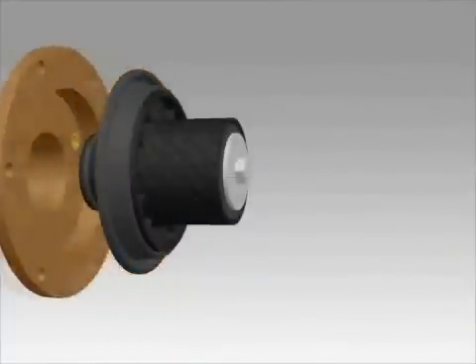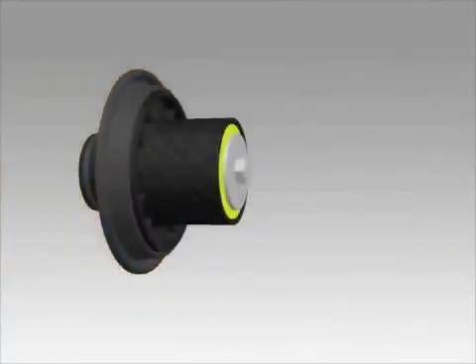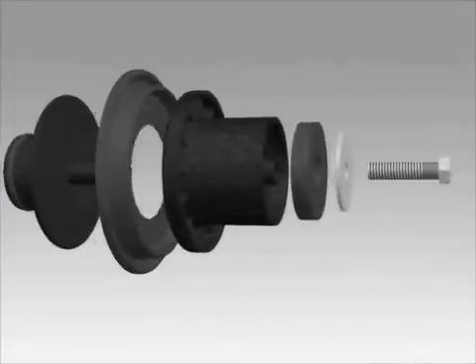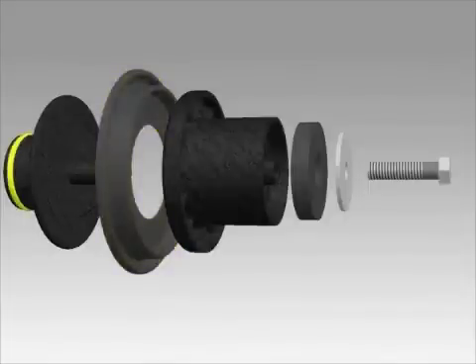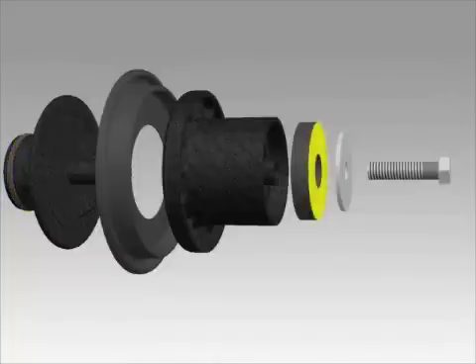Gently pull the cartridge from the relief valve cover. Inspect the seal ring for any cuts or embedded debris. You will want to disassemble the cartridge by unscrewing the seal ring retainer screw. Inspect the diaphragm closely for wear or holes. Inspect the O-ring on the upper plunger for any cuts or damage. Remove the seal ring and inspect the face for cuts or embedded debris.